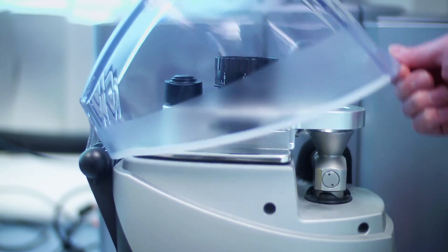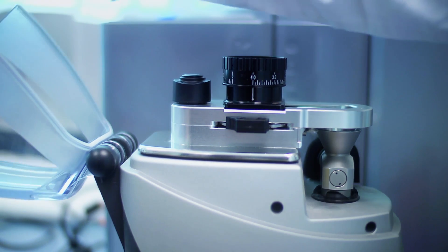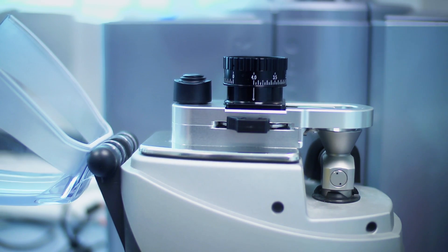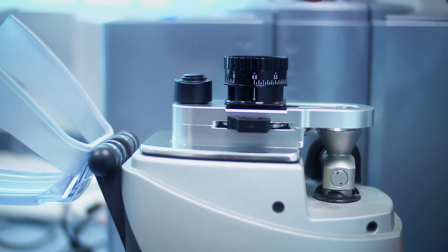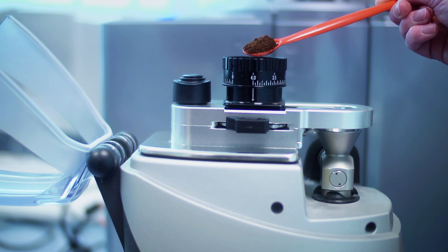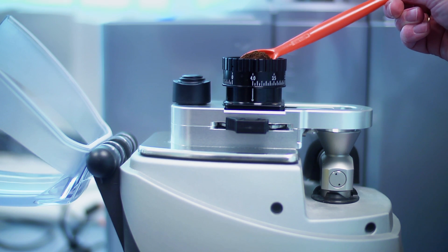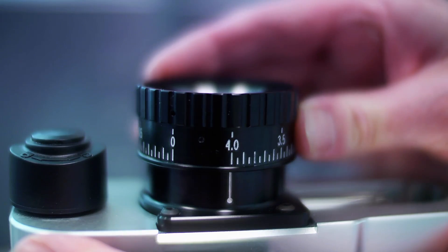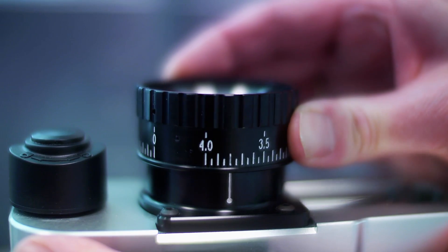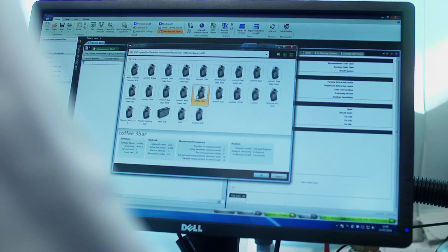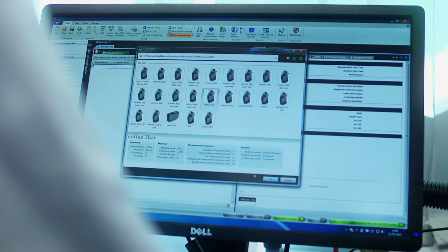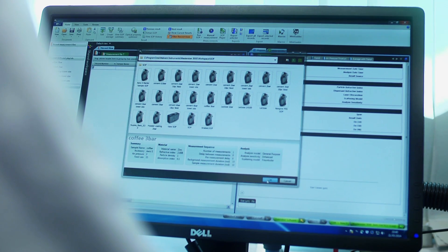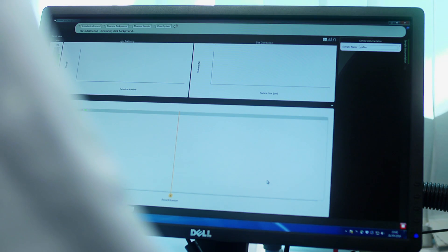Dry measurements offer the ability to quickly measure larger volumes of sample. The sample tray and hopper can be configured to control the flow of different types of material. Other sample trays are available to handle smaller sample volumes. As with liquid dispersion measurements, the Mastersizer 3000 measurement manager is used to guide you through the dry measurement process.